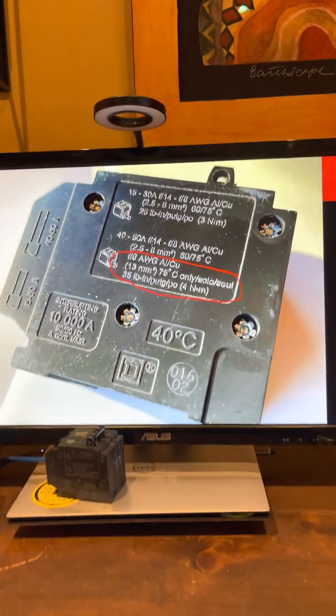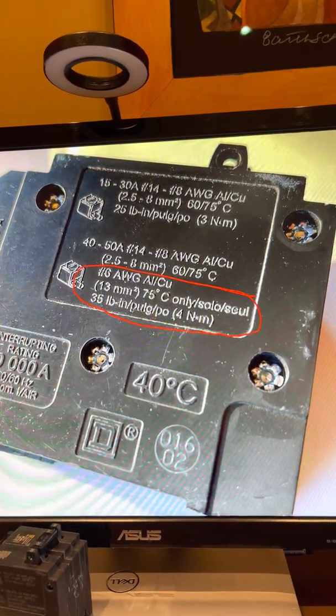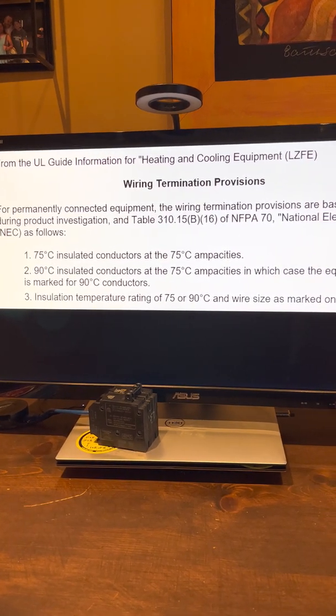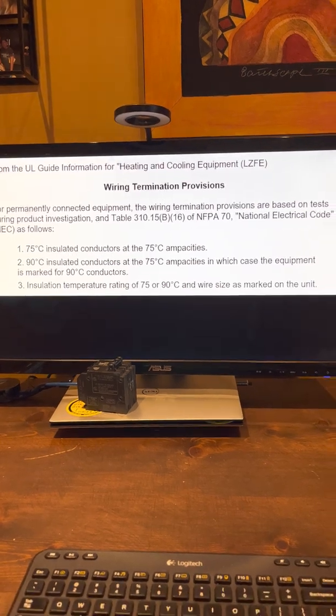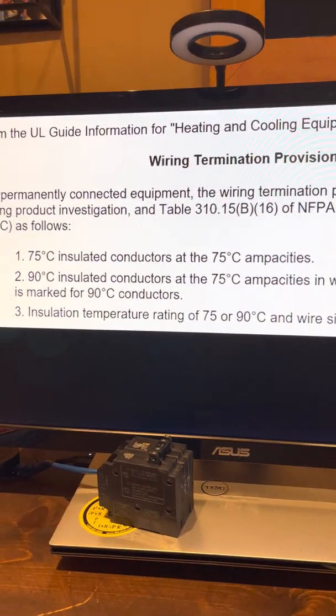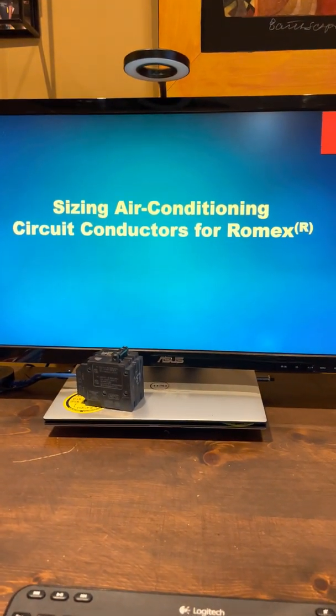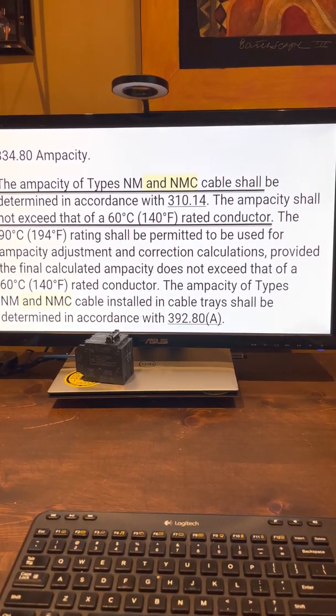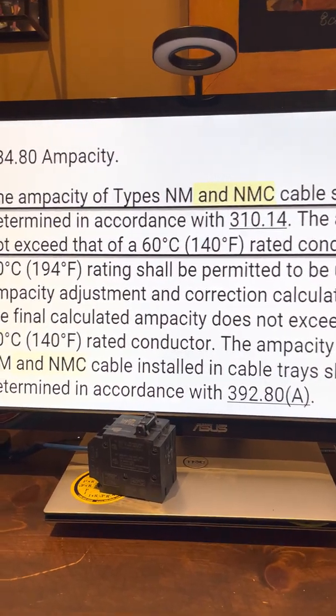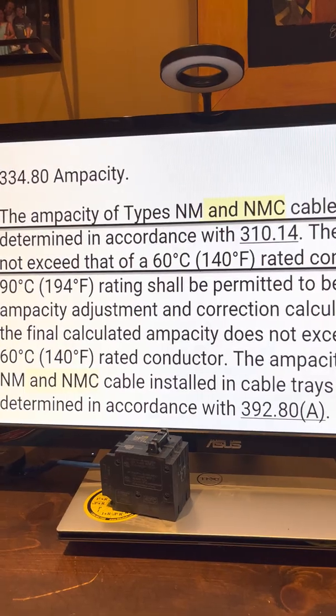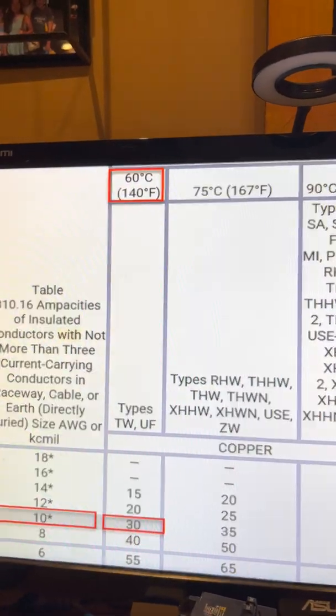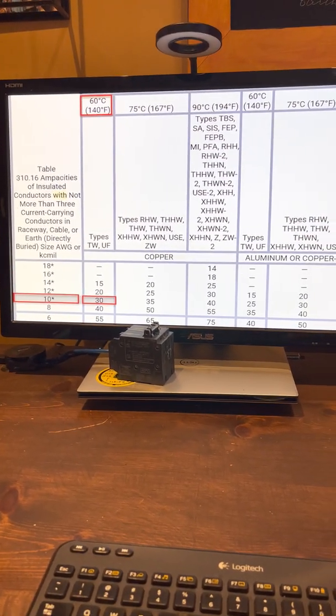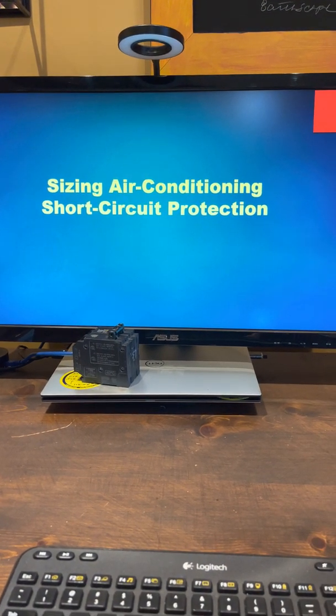How do we know it's 75 degrees C? All circuit breakers are marked 75 degrees C, so we use the 75°C column of Table 310.16 in the 2020 code. UL guide information for heating and cooling equipment states that all terminals for heating and cooling equipment are rated for 75 degrees C, so we size the wire to 75°C. However, if you use Romex, 334.80 requires you to base it upon the 60 degrees C column. Even though the terminals are rated 75°C, with Romex we go to the 60°C column — in that case, 10-gauge wire would be suitable for the 24-amp minimum.